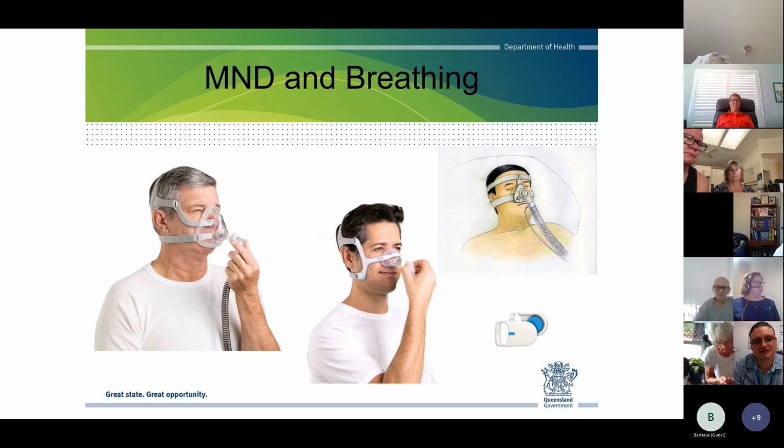You can see it goes over the nose and the mouth. And that's for people who mouth breathe quite heavily. So if I'm ventilating through the nostrils, that air is just going to come straight out the mouth if you've got a wide open mouth all night. I can add little chin straps to hold the mouth shut, or we just go to this full face mask, and it's a lot more invasive on the face.